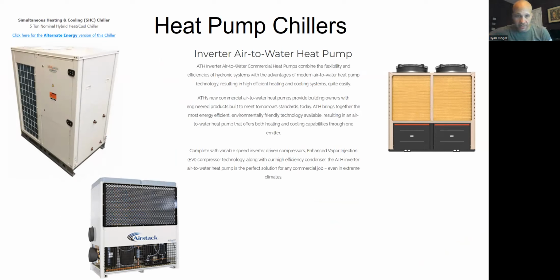Even on this screenshot I did, they were calling it air to water heat pump. All right, so that is what most of us would call an air cooled chiller. That's a heat pump, air to water heat pump. Remember on module 1, we had air to air, water to air, water to water. This particular one is an air to water heat pump. We could also have a water to water heat pump that is a chiller.